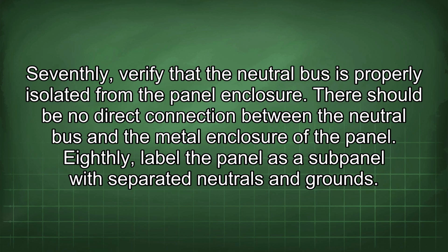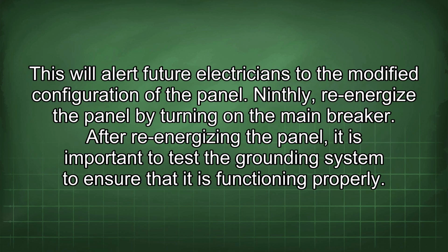There should be no direct connection between the neutral bus and the metal enclosure of the panel. Eighthly, label the panel as a subpanel with separated neutrals and grounds. This will alert future electricians to the modified configuration of the panel. Ninthly, re-energize the panel by turning on the main breaker. After re-energizing the panel, it is important to test the grounding system to ensure that it is functioning properly.